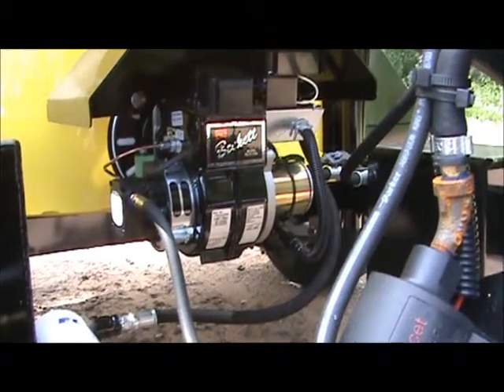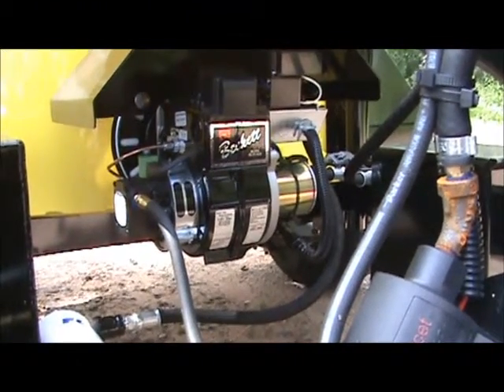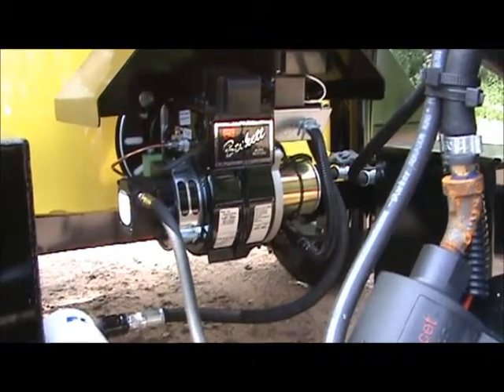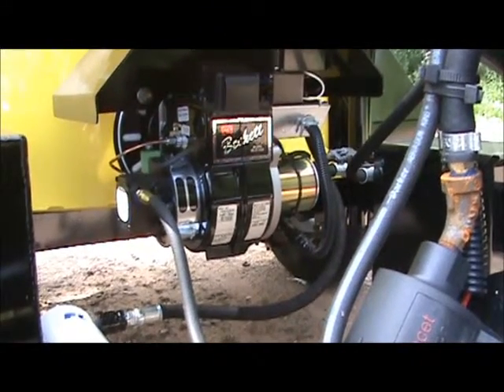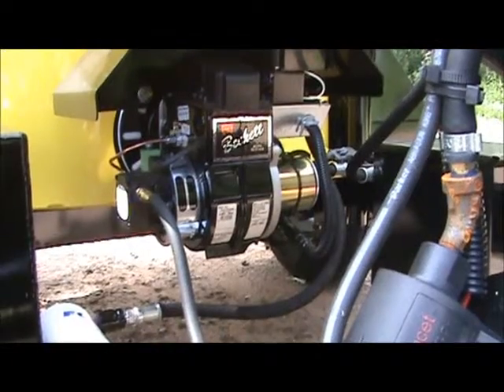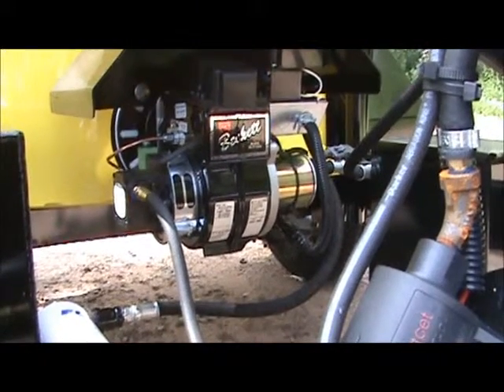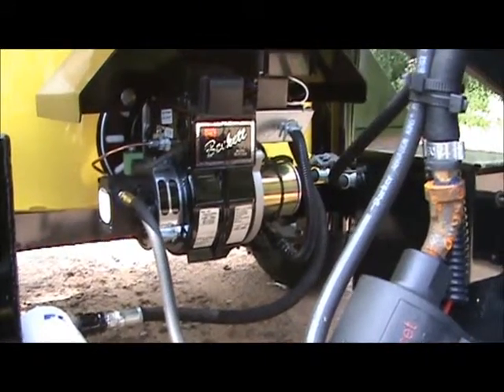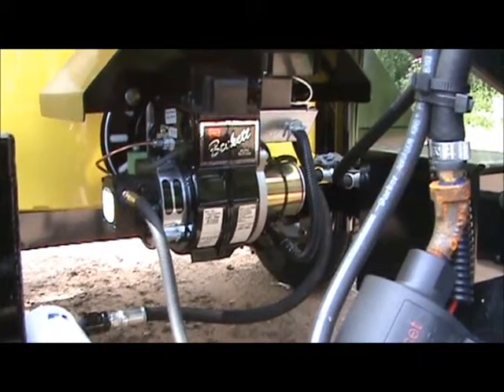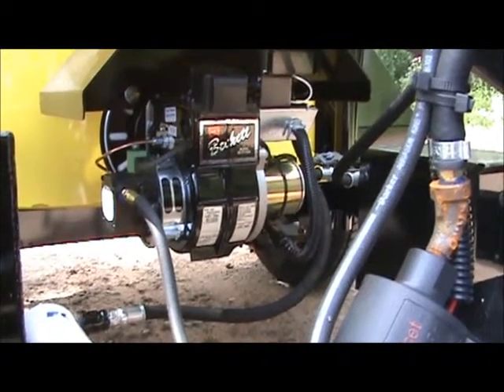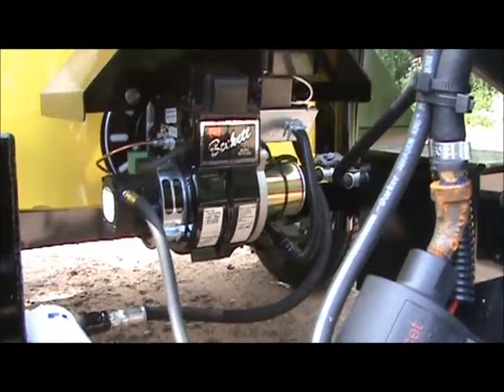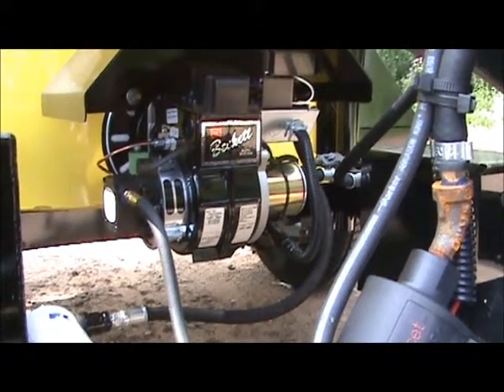The burners are a very simple device to work on, very simple to operate. They're very durable. A couple of the main things that cause burner problems, one of them is no voltage, just no power or low power. The other one is no fuel. So we always diagnose those problems first. Let's check to make sure we got power to the burner. Let's check to make sure we got fuel.